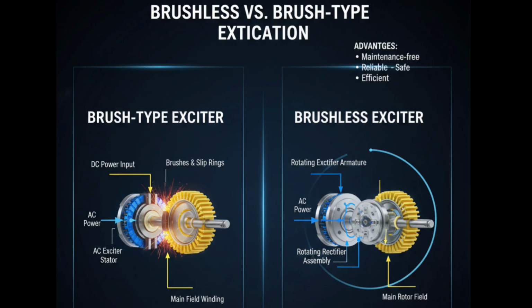In brush-type exciters, brushes maintain contact with slip rings to deliver DC to the rotor field. While this works, it causes friction, wear, and sparking. Maintenance is frequent, and operational reliability decreases over time, especially in marine applications where vibration, humidity, and saltwater can worsen wear and corrosion. The brushless system, by contrast, eliminates brushes and slip rings entirely.